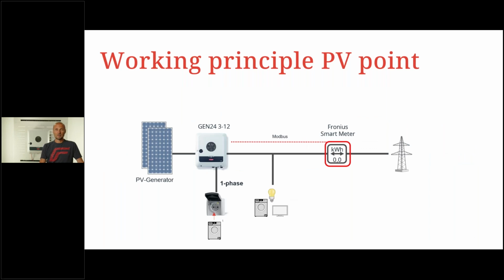The working principle of the PV Point is that we have a specific output socket on the Gen 24 inverter, and there you have your 230 volt socket. With that, you supply your loads in the household, so your specific loads which you need, especially in the grid outage moment. As you can see here, we don't need a battery. It's just a socket, a cable which is connected on the inverter. And here we connect our socket, and on the socket we can plug in all the loads we need.